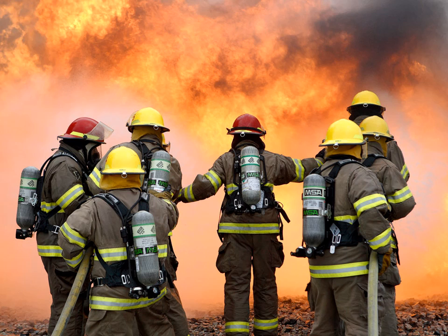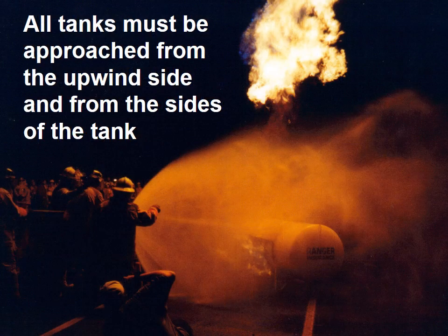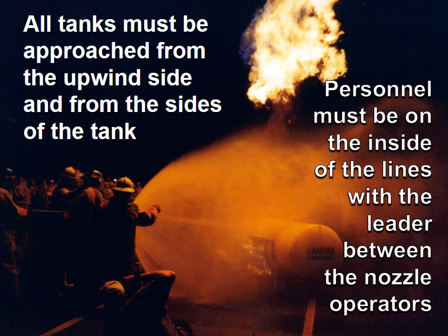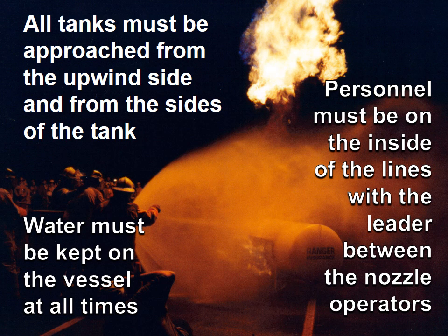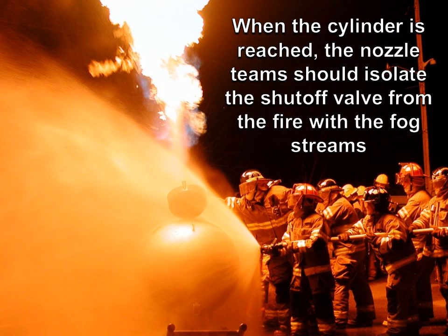Wearing full PPE, two teams of firefighters using a minimum of two 1.5-inch lines should advance using wide overlapping fog patterns. All tanks must be approached from the upwind side and from the sides of the tank. Personnel must be on the inside of the lines with the leader between the nozzle operators. Water must be kept on the vessel at all times.